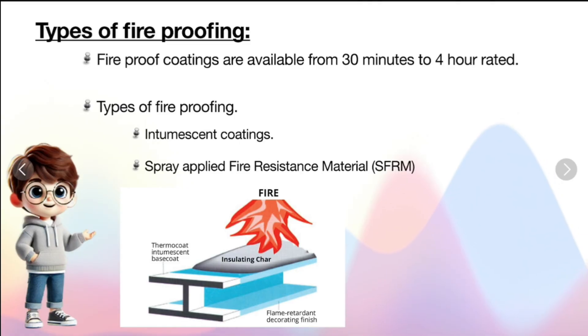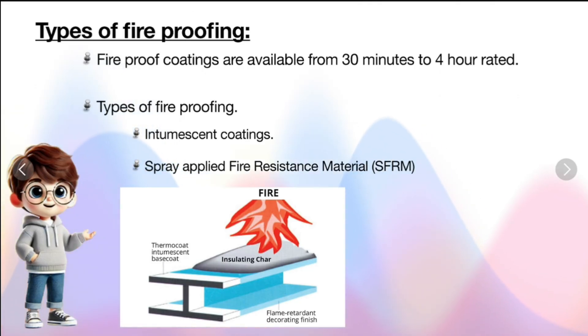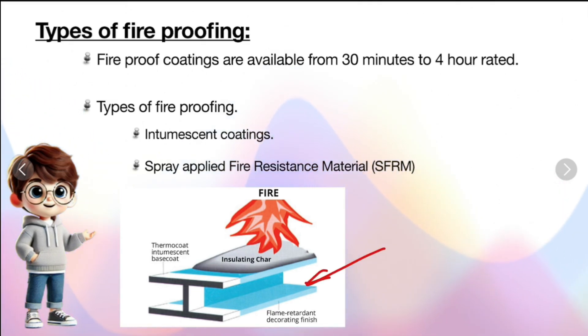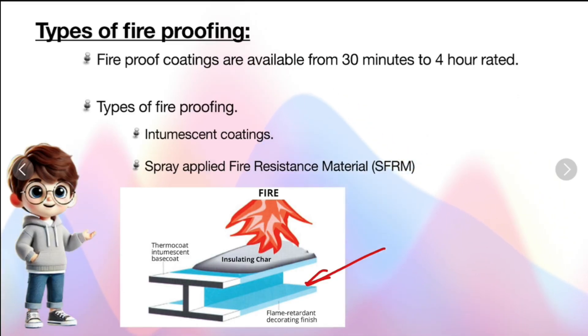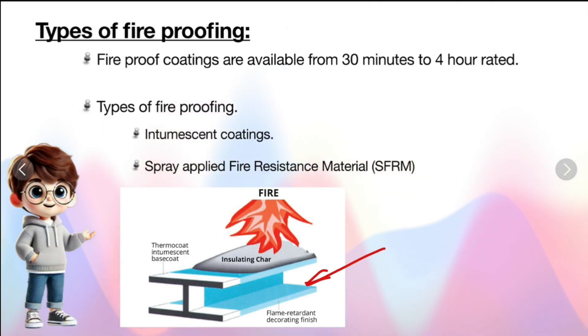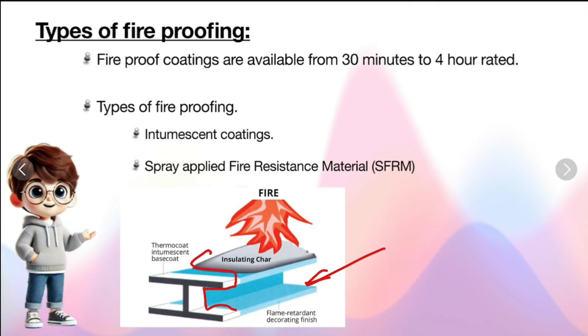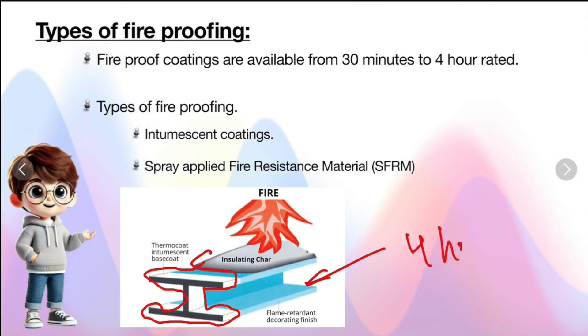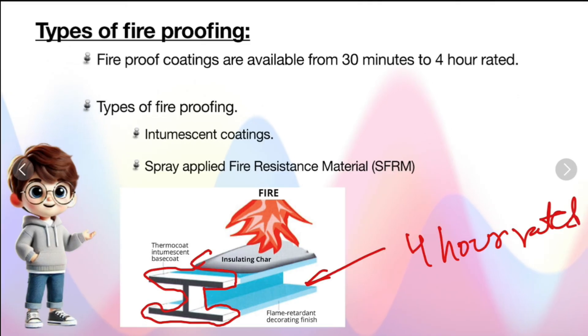First we look into intumescent coating. This blue color one is the intumescent coating — there is a thin layer of intumescent coating that we apply on the surface of steel. When steel is caught by fire and reaches high temperature, this paint will expand and form an insulation coating all around the steel. It can be up to 4-hour rated, but it is a costly process.